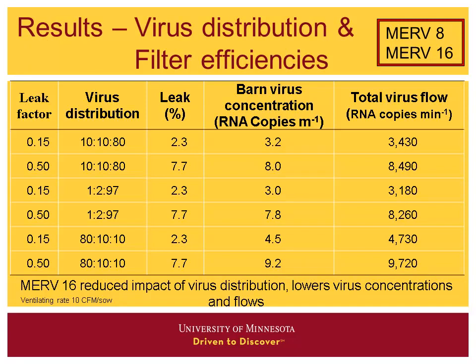Looking at different virus distributions with MERV 8 plus MERV 16: we are now collecting about 97% of those very small particles in the 0.3–1 micron range. With the MERV 16, the total virus and virus concentrations across different distributions are very, very close to each other. So MERV 16 reduced the impact of the virus distribution and lowers those virus concentrations and flows. The model indicates that using a very good filter removes a lot more virus, especially at these infiltration rates.